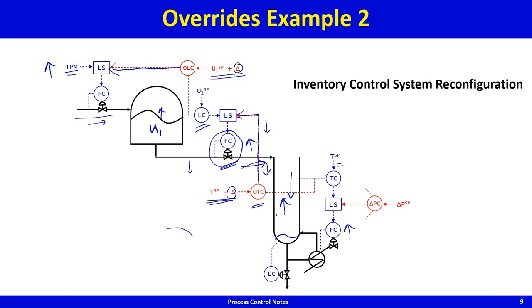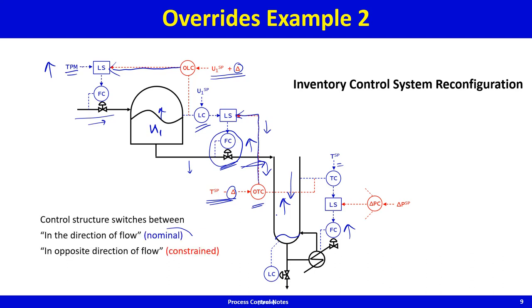Because level control has been lost and feed is still coming in, the level goes up. An override level controller detects this; when the level rises above its set point, that signal becomes the lowest and feed is cut to only as much as can be boiled off in the column. The control structure has switched — from the nominal blue loops (in the direction of flow) to the red loops (opposite direction) — governed by these overrides and carefully positioned low selector blocks.